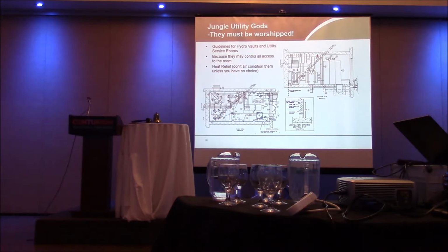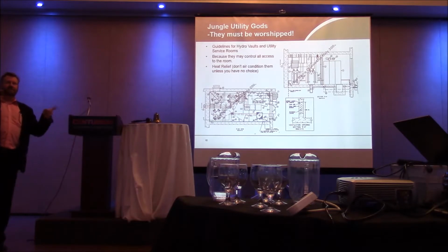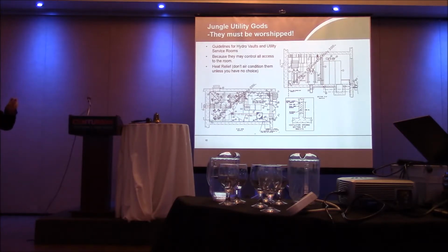So it can get pretty damn hot in that electrical room. You're going to break a sweat. The other reason I'm seeing rooms air conditioned is because there is some electrical equipment, such as UPS systems, that won't work at 40 degrees Celsius. Okay? It gets pretty unhappy much beyond 25 degrees Celsius, and so we air condition the UPS room.